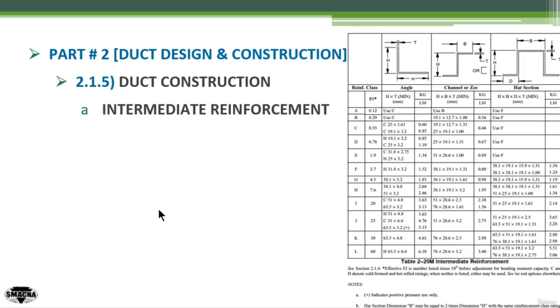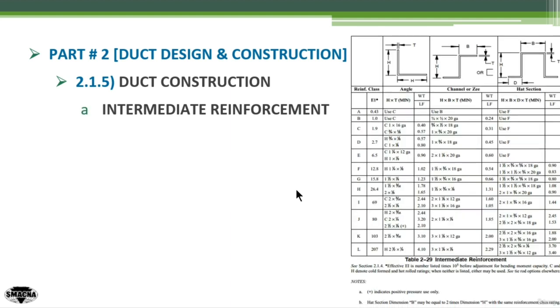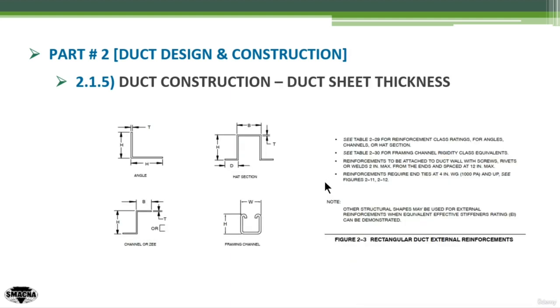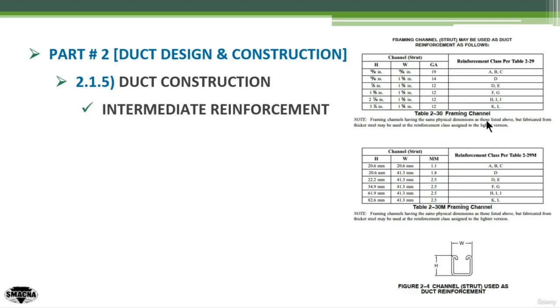We can use the reinforcement class as the entry point to get all the details. For example, if I'm going to use reinforcement class F, this will give you angle details of specific dimensions, a Z-channel of specific dimensions, and a hat section of specific dimensions. And in Table 2-30, which was referred to in the reinforcement requirement notes — see Table 2-30 for framing channel rigidity class equivalents — going back to this table, which is Table 2-30 for framing channel or slotted channel, this table gives you the dimension equivalents of the slotted channel and the gauge requested based on the reinforcement class, represented in the last column.